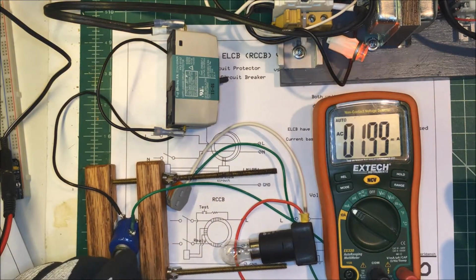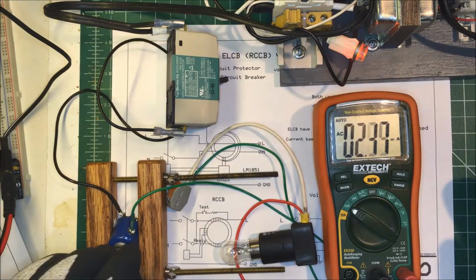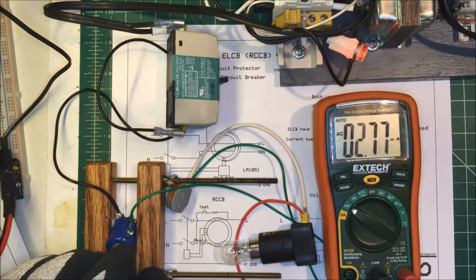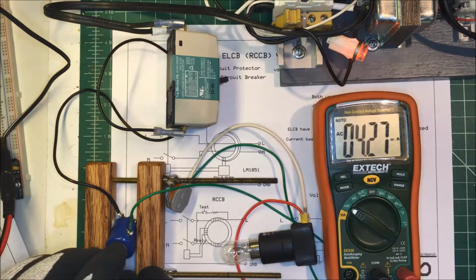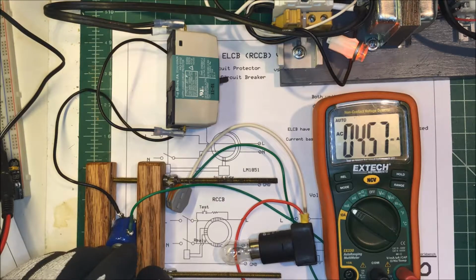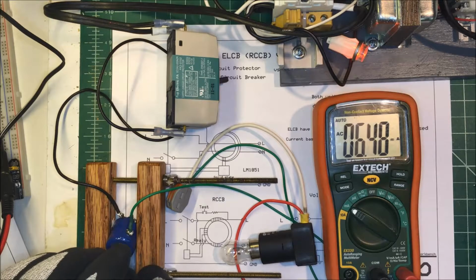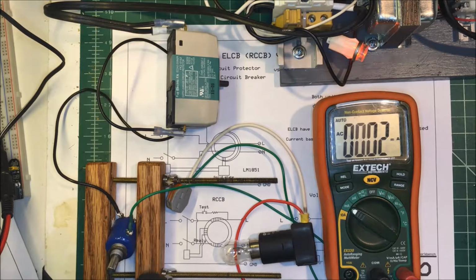And if I crank this up, we've got 2, 3. Now I'm expecting it to go off around, it says that it's good for, it'll trip before it gets to 10 milliamps. I've got 4 milliamps, 5, 6, there we go. I think it went off at about 7 milliamps. I'll play that back and take a look at it.